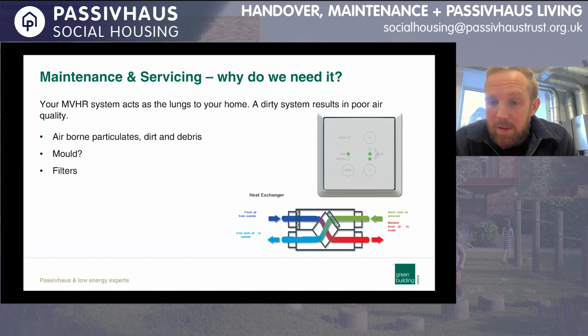So with regard to controls, there's a picture there of a controller which I've just put in. That is what we tend to use in social housing. So they can choose between fan speeds. They can boost the system, perhaps when we're cooking, and that will increase the airflow rate for a set period of time, usually 45 minutes, and then it'll go back down to standard operation. As you can see on that controller there, it does have an LED light that will flash on the filter section when the filters need changing. It does obviously need someone to do something about that. Some people might see it flashing and ignore it.